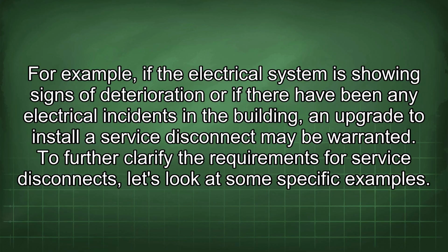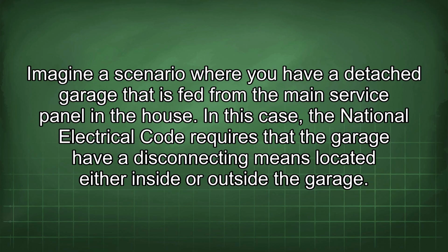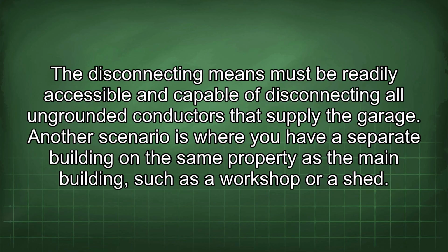To further clarify the requirements for service disconnects, let's look at some specific examples. Imagine a scenario where you have a detached garage that is fed from the main service panel in the house. In this case, the National Electrical Code requires that the garage have a disconnecting means located either inside or outside the garage. The disconnecting means must be readily accessible and capable of disconnecting all ungrounded conductors that supply the garage.